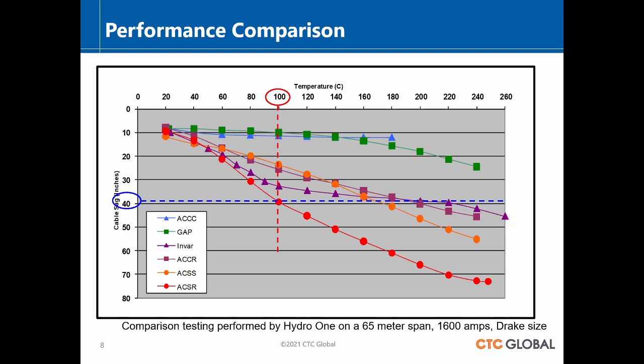And you can see, certainly as it ran on out, you wouldn't run that ACSR at those higher temperatures because the tower is not tall enough. That point is what determines if I'm going to use an ACSR and I'm going to run it at 100, I know its sag. I've got to have a clearance and a safety, and voila, that's the height of my tower. And those are the heights of the towers that you see around, designed with those kinds of constraints.